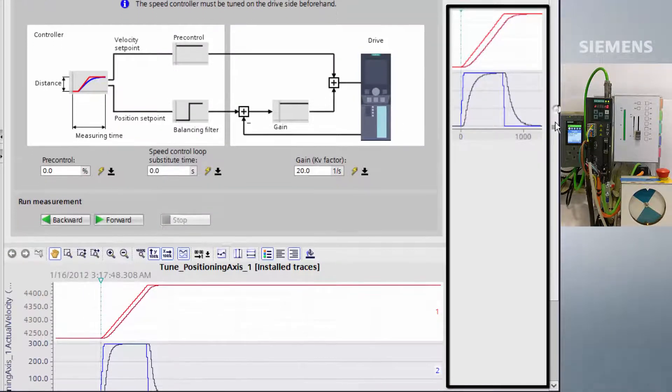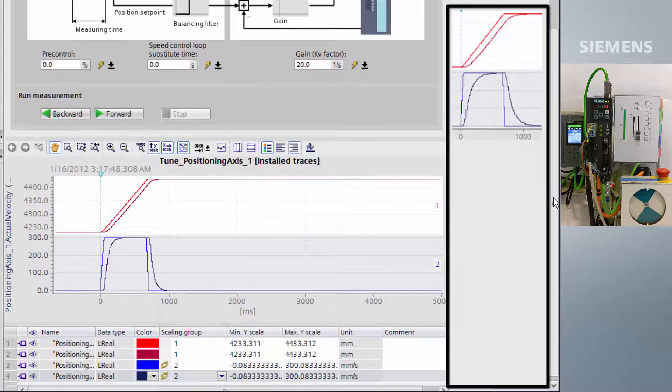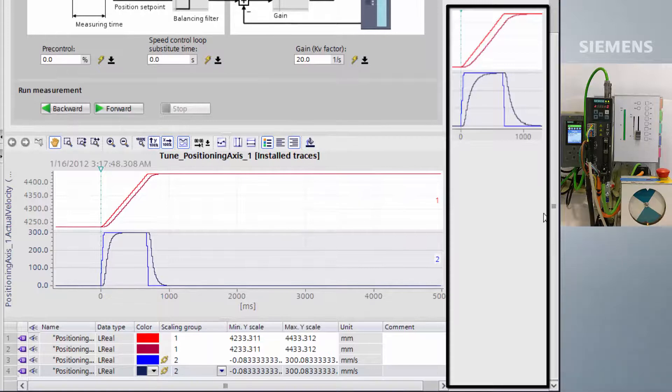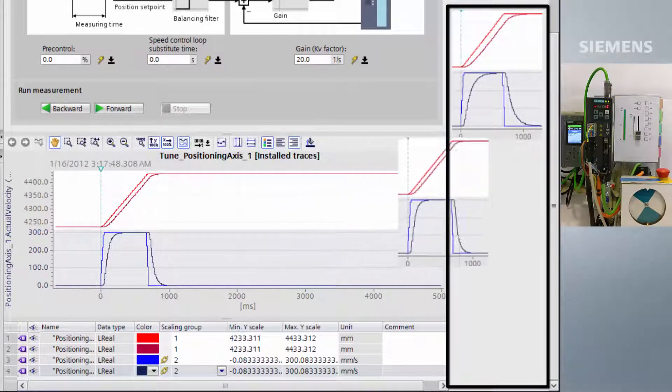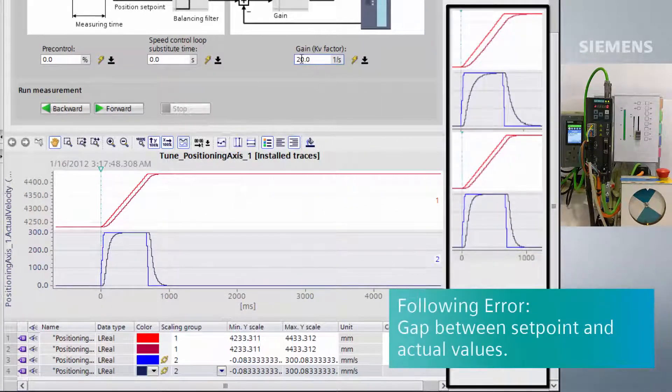As we can see, the gaps between the graph lines have become much closer together. This gap is known as following error. Reduction in following error improves the dynamic performance of the drive.